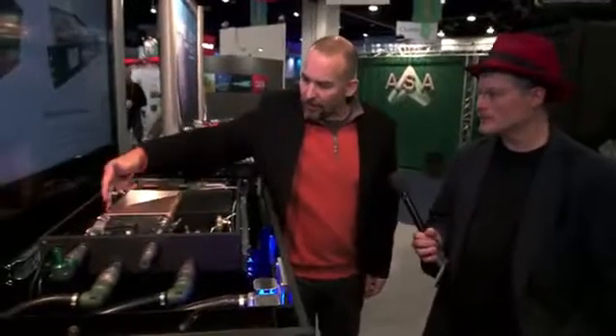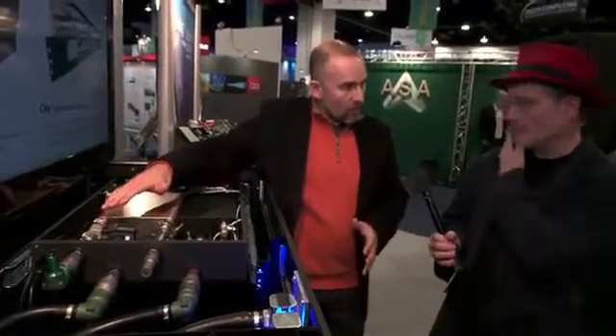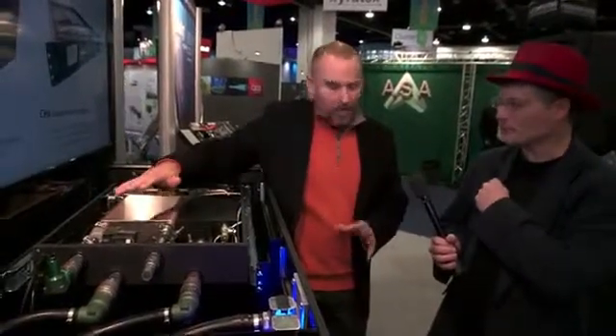That cool liquid is then exiting back towards the cold side manifold. The facility water is actually what's providing the cooling. That enters in here. We have a proportional valve so that in the event that we have chilled water supply, there's actually a risk. If we allow that to flow freely, it could overcool the coolant.